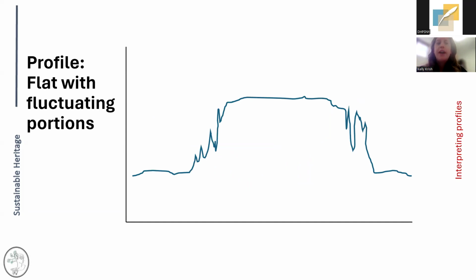Okay, and the fifth profile and the final one is you can see that we have flat portions in both the winter and the summer. So in this instance, we have a mechanical system that's capable of dehumidification and capable of humidification. But what we are seeing is the fluctuations in what I'll call the shoulder seasons, so spring and fall. If you think back to that graph that we had, where there was that band between when we dehumidify and when we humidify, that's what it looks like when we're looking at data from a space. Essentially, it's humid enough that we're not calling for more humidity, but it's not so humid that we're calling to dehumidify. It's kind of coasting in that band.